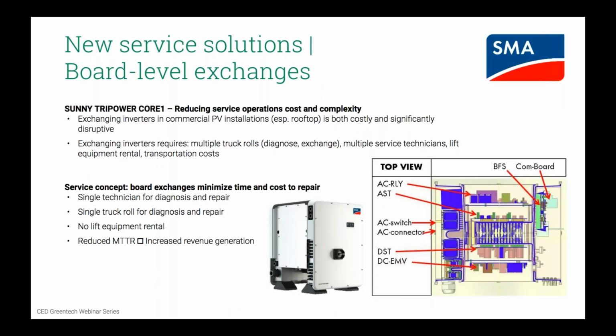When we were bringing the SMA Core 1 to market, even during conceptual development, customers told us clearly that the traditional approach of servicing string inverters by replacing them was particularly challenging in commercial installs where inverters are located on the rooftop or in carport systems high up off the ground underneath the canopy. Doing an inverter swap there requires getting heavy lift equipment to the site, scheduling around building operations, like the school day at a school, or a retail operation's hours.